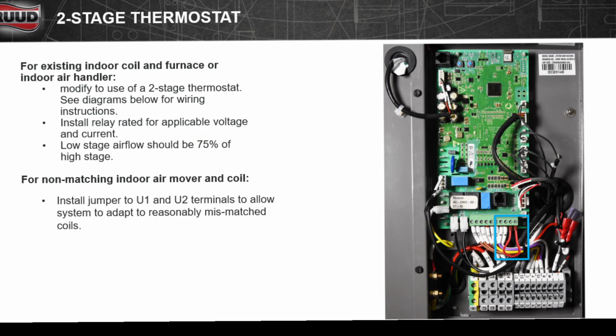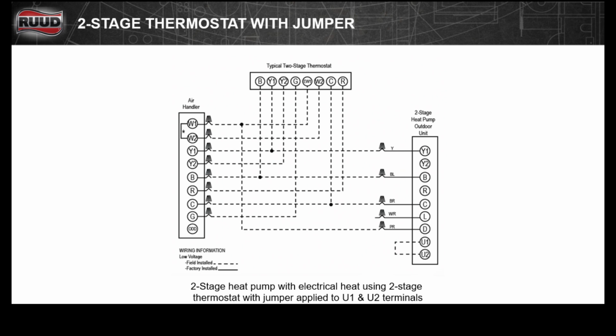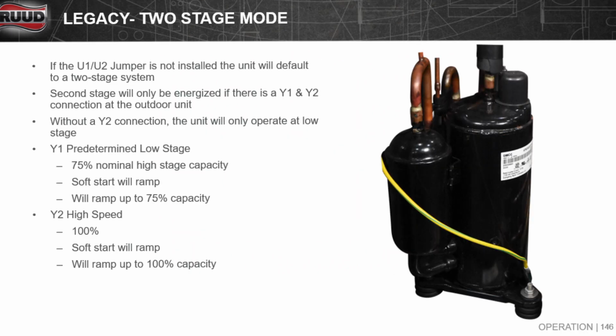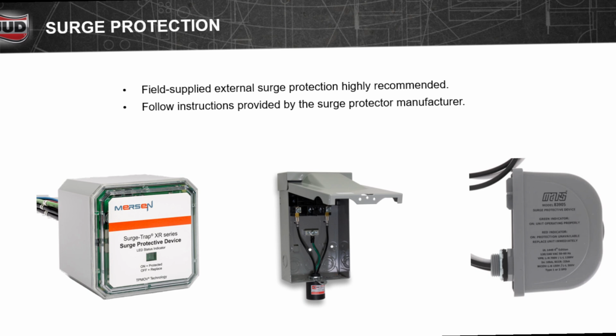Once activated, the Ruud algorithm will attempt to maintain a 45-degree suction line saturation temperature. With U1 and U2 jumped out, you only need 4 wires to connect this in legacy mode: Y1, B for the reversing valve, brown for common, and D for defrost. If the U1 and U2 jumper is not installed, the system will default to a 2-stage system, Y1 being 75% and Y2 100%. And of course, on any variable speed inverter system, surge protection is an absolute must. Please protect both the indoor and outdoor units with surge protection.